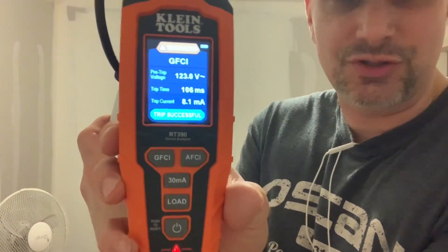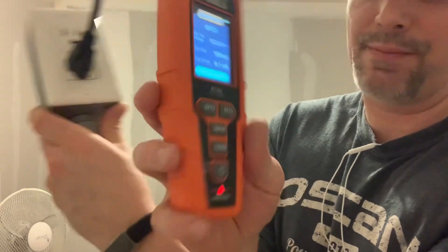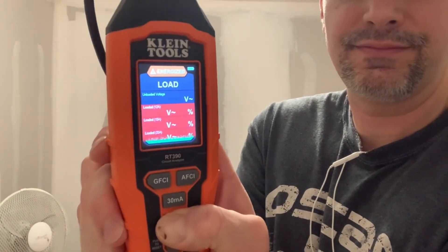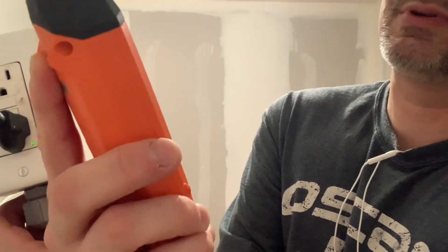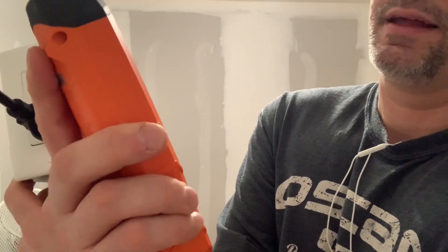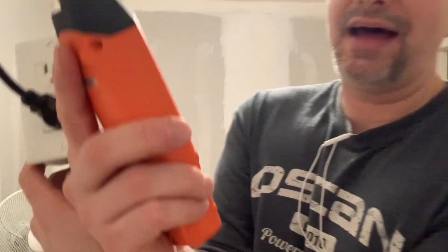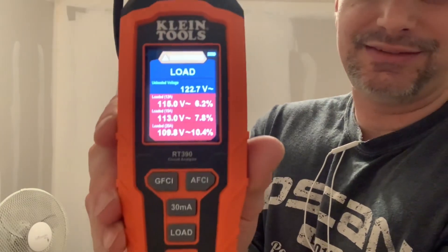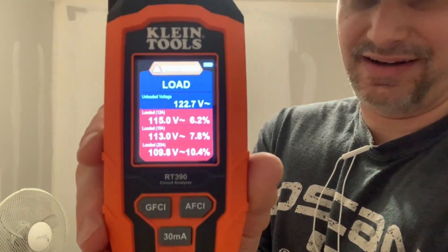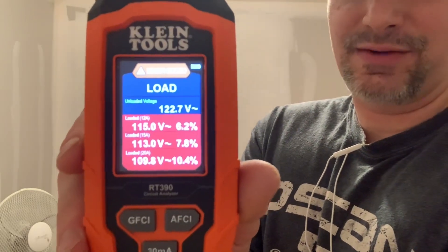Now I want to check the voltage drop using the load mode. I'm expecting a voltage drop because I have a 16 gauge extension cord in line — the cord itself is 12 gauge but it's plugged into a 16 gauge extension cord. Running the load test: it's showing 6.2 percent voltage drop on a 12 amp circuit at 115 volts, 7.8 percent on a 15 amp circuit, and 10.4 percent on a 20 amp load at 109.8 volts. You want to stay under five percent, so six percent and higher tells me this cord is probably not the right cord for what I need.